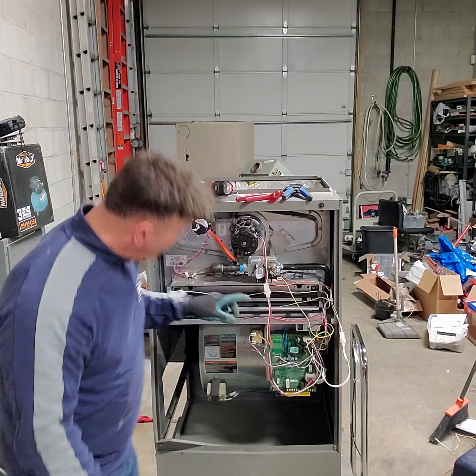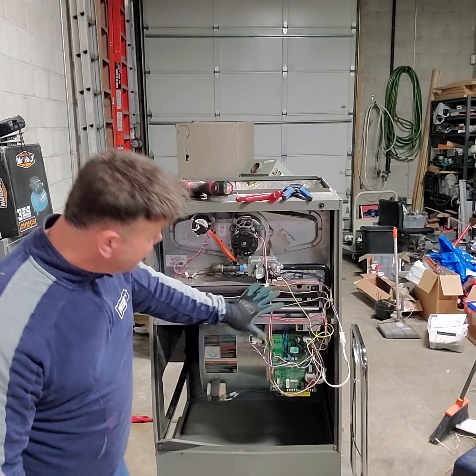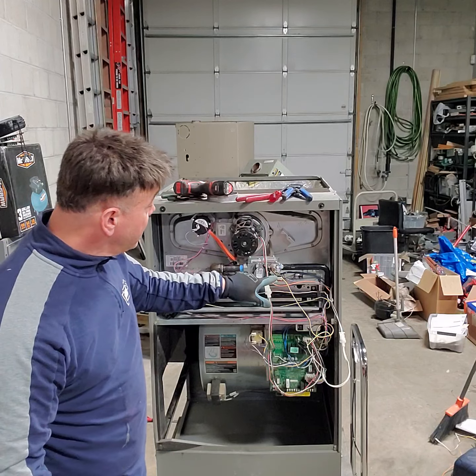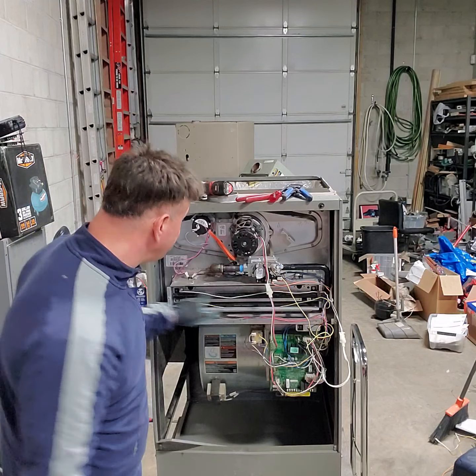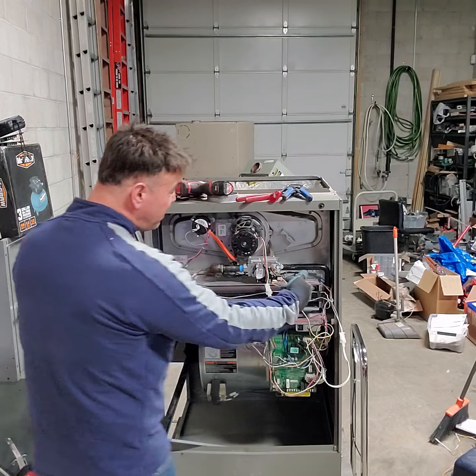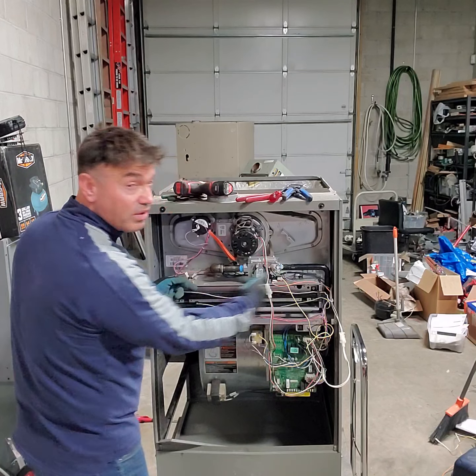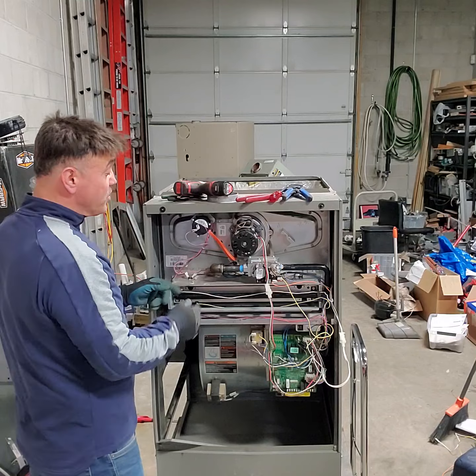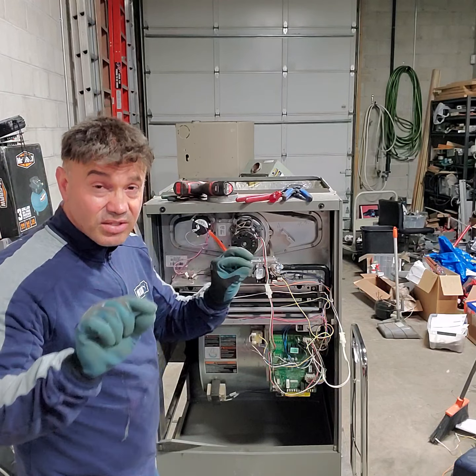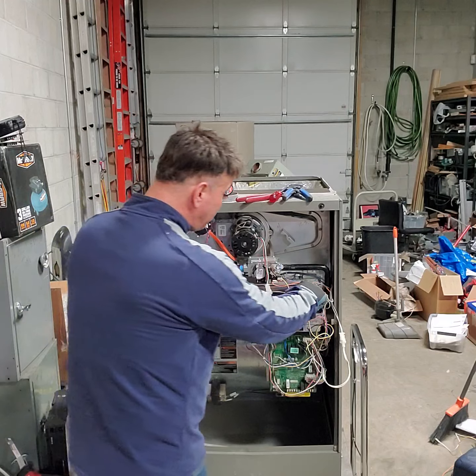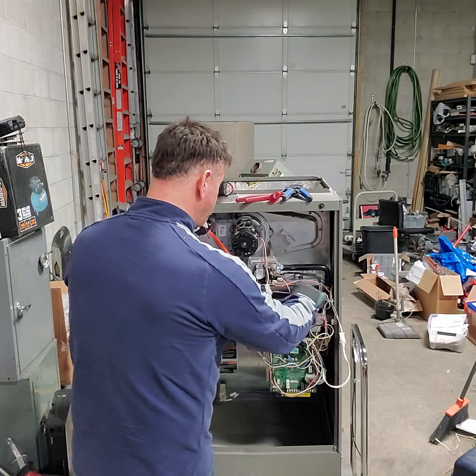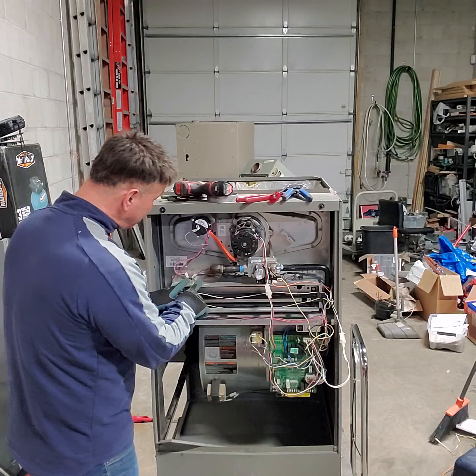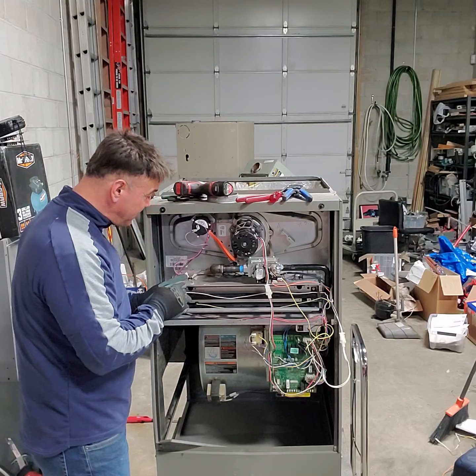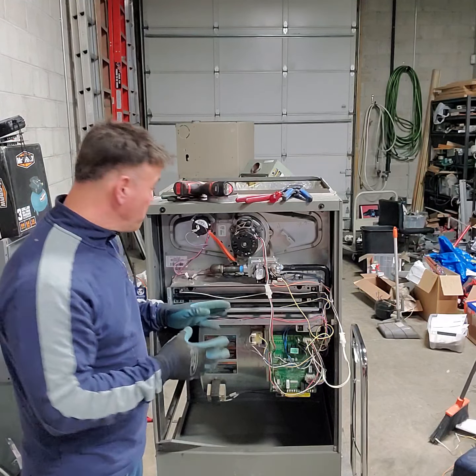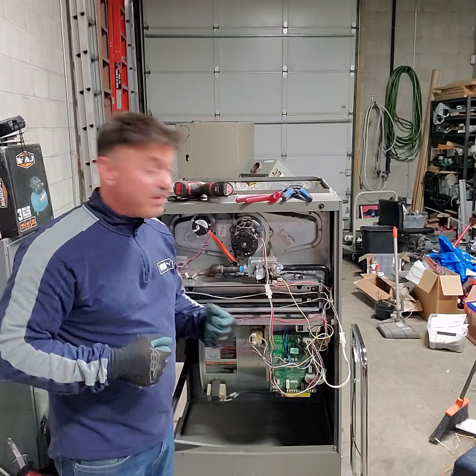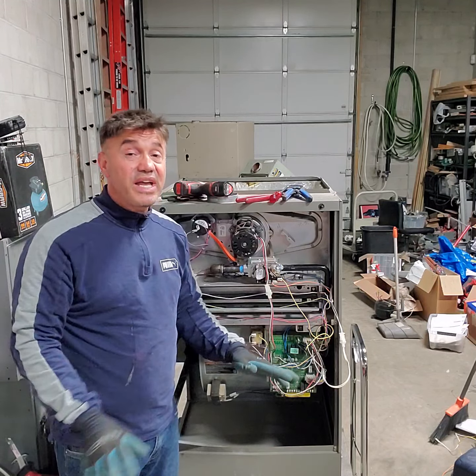If you look at it, on this one you can't see it, but on most others you can. When the igniter comes on, you can see the flame go from that way and immediately connect to the other one and ignite the others. Sometimes if that very tiny path is clogged, it only fires 2 of these injectors, and then the one that's supposed to be shooting on the flame sensor doesn't ignite. So the flame sensor sends a message to the control board: hey, we have fresh gas, stop immediately.